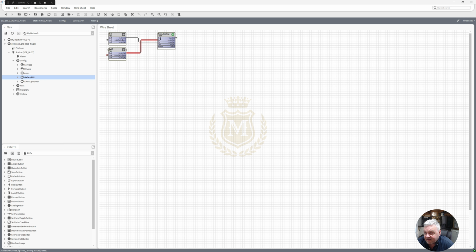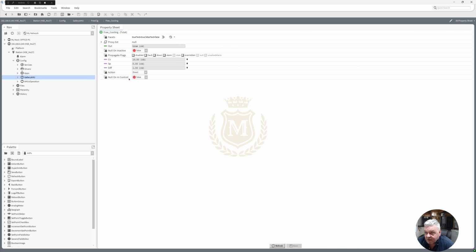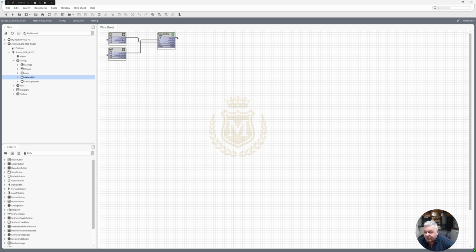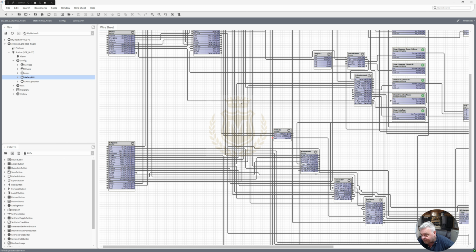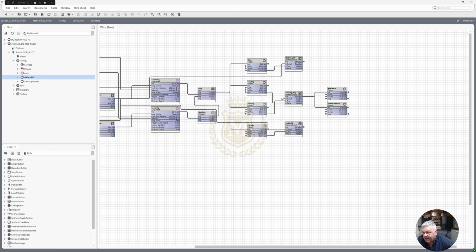It's a free cooling T-stat there that we've used. You can see the differential there is 1. Maybe that should be 2, 1 degree either side, but we've left it at 1 here. And that free cooling is actually on at this moment in time, because outside air is lower than the inside air. And if we follow this through from the free cooling, it will go into this supply temperature folder, and there's my in switch there, which is true. So if it's true, it's using this.